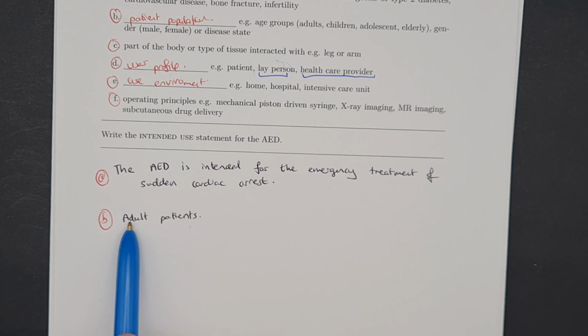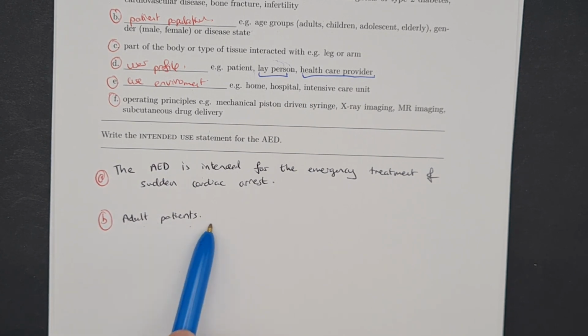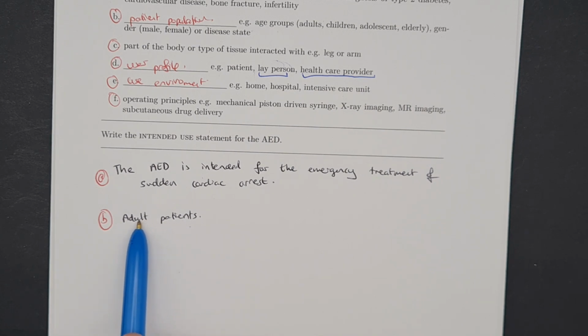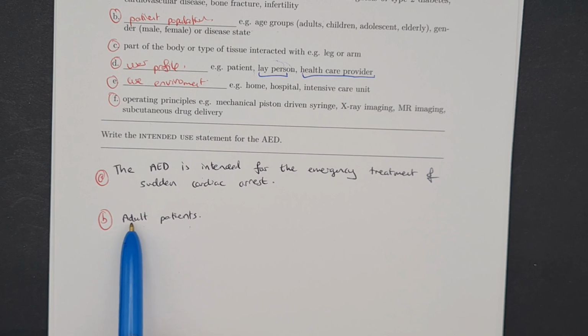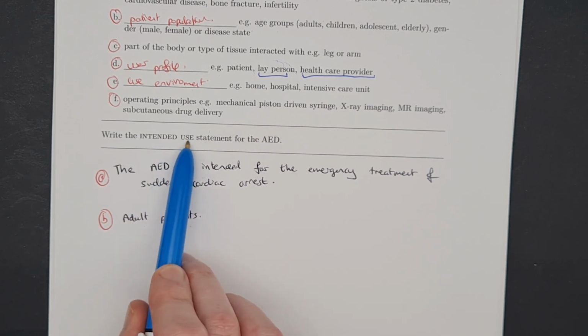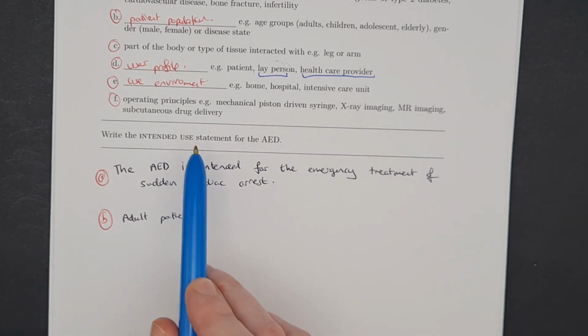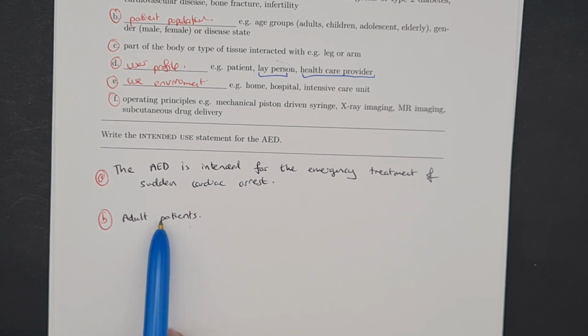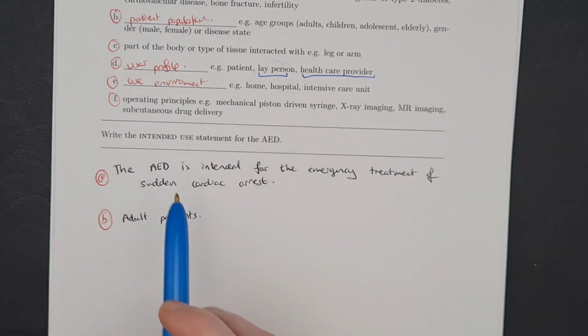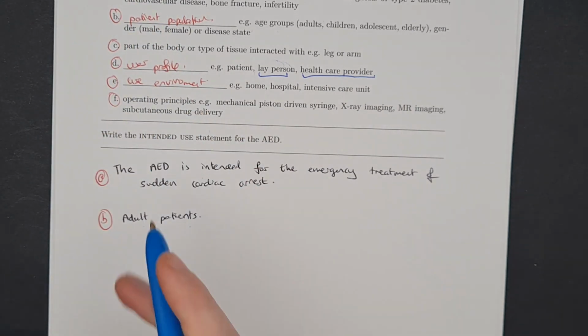And then provide warnings it's only meant for adults. If you decide it's meant to be used for adults and children and pediatrics, you're now going to need to gather evidence that it actually performs as intended on the adult population and the other populations. So you do have to be a little bit careful that the more you add to your intended use, of course, the more the device can do, but the more testing you're going to need to do, especially validation testing, as a result of how you have written this statement. So you have to be quite careful in how you write this. So that's A, B.